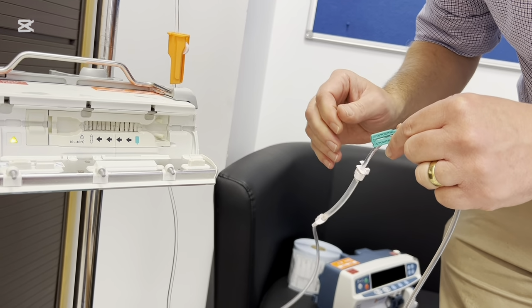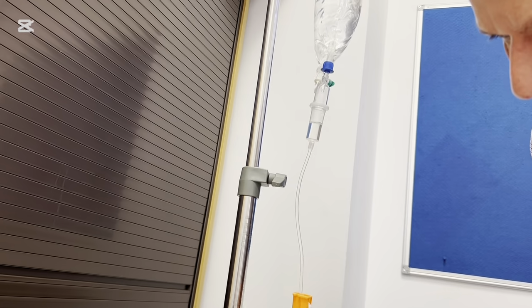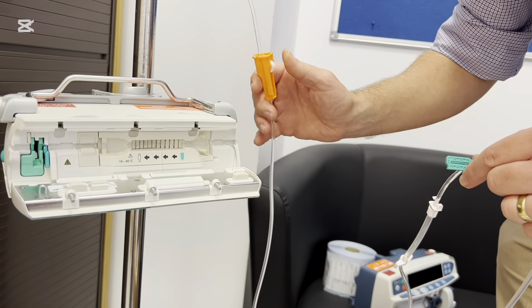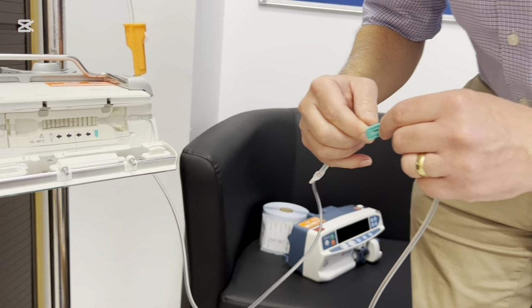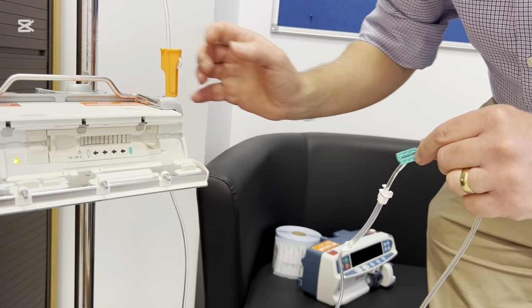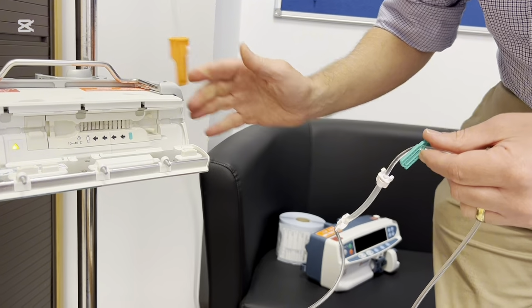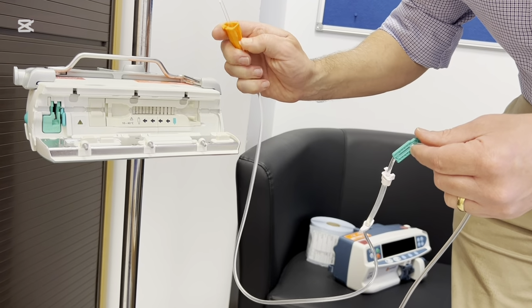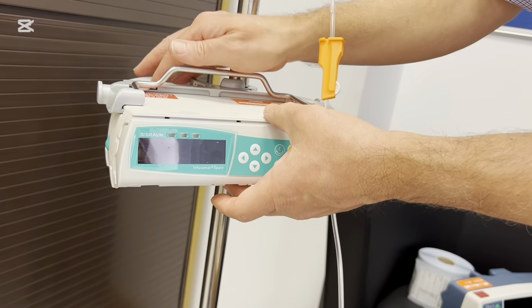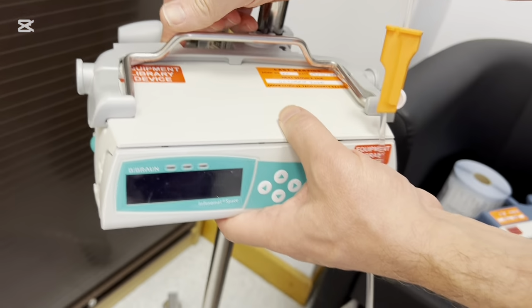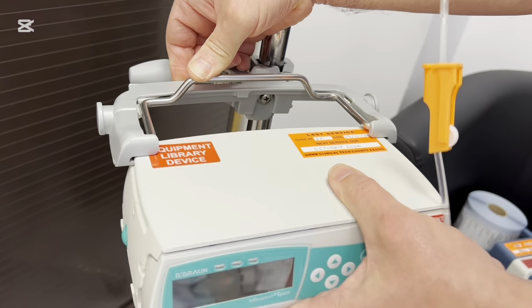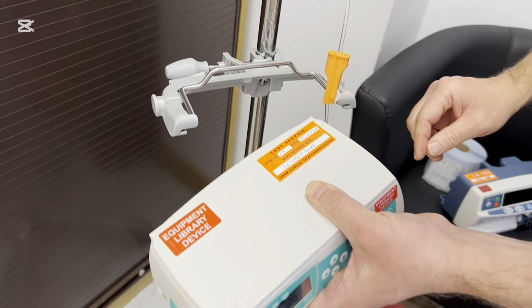So you can then just open that and it will just run as an ordinary gravity set rather than having to change and use another gravity set. But obviously, because it doesn't have any mechanism to prevent reflux, if you're using it as a gravity set against an infusion pump, you might want to consider an anti-reflux line. Okay. To remove the pump from the stand, depress the white clip, slide that down, and the pump can just easily slide out of the holder.